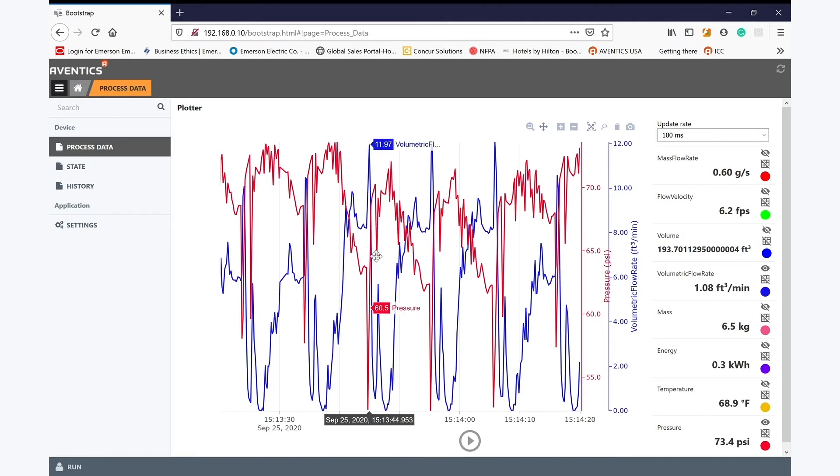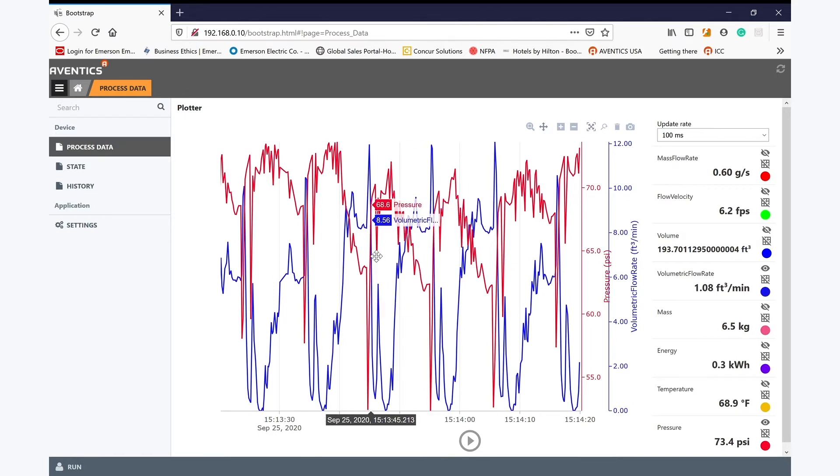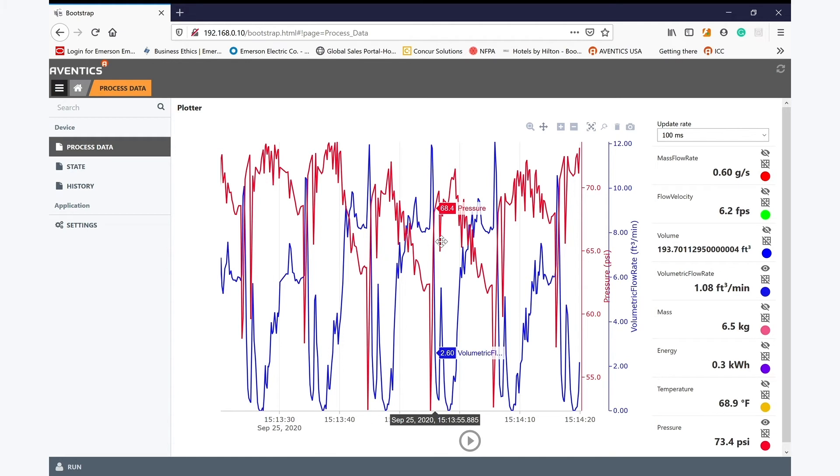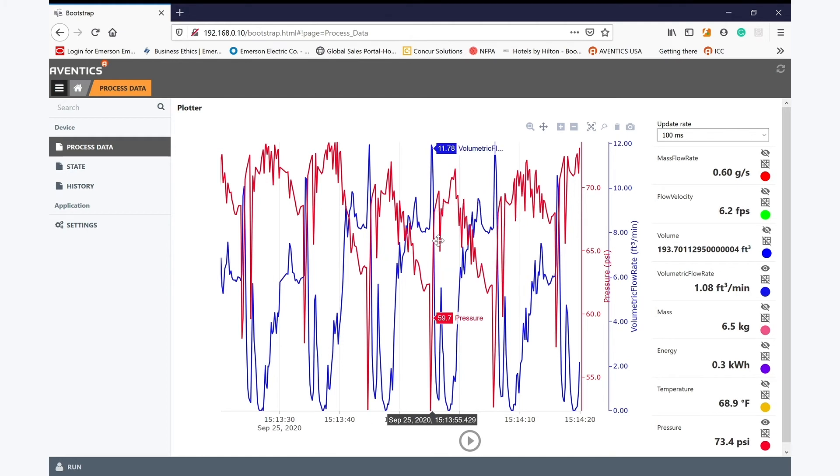I can use the tools within the AF2 to see my flow has increased from 10 to 12 CFM. Also, I'm seeing a pressure drop at the same time, further indicating I'm losing compressed air.